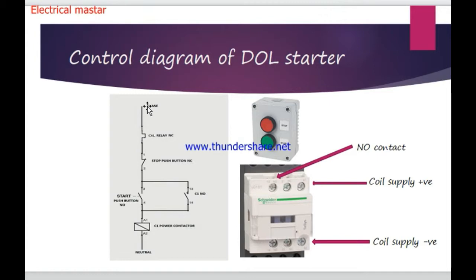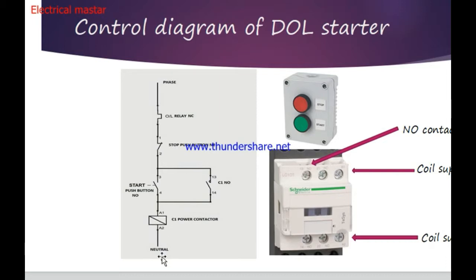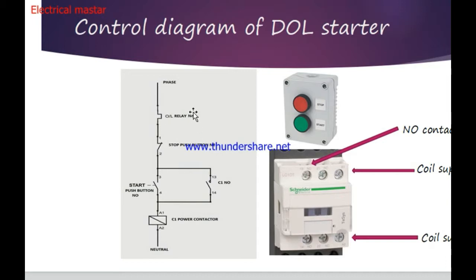Looking at the control diagram, a single-phase supply is connected to the magnetic contactor coil supply — the control supply is 240 volt phase and neutral line, a single-phase connection. In a DOL Starter we can also use 110 volt DC or 110 volt AC. At 240 volt AC, there is a phase line. The overload relay is connected via a normally closed (NC) contact, so normally when there is no fault, the NC contact is closed and connected.